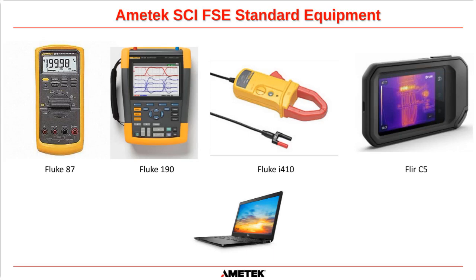Okay, so here is the equipment that every single one of our field service engineers carry with them. So they carry a Fluke 87, they carry a Fluke 190 oscilloscope. It's just a dual channel oscilloscope. We carry a Fluke i410 amp clamp, a FLIR C5 camera, and at this moment in time, we are using laptops to connect to all of these devices, but we are going to be moving over the next year or two to iPad Pros. We are in the process of changing over to iPad Pros to make the maintenance go smoother and easier. But that is the minimum of equipment that our guys carry. Most of our guys carry more than 1 amp clamp, but that is the minimum that they carry.